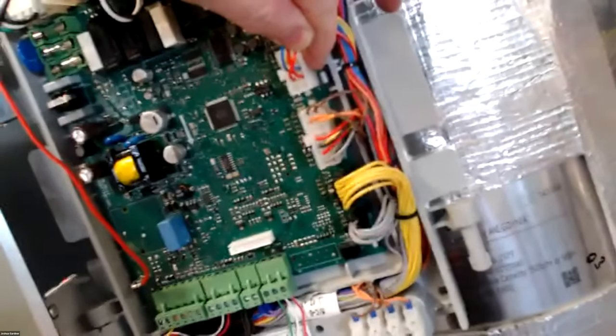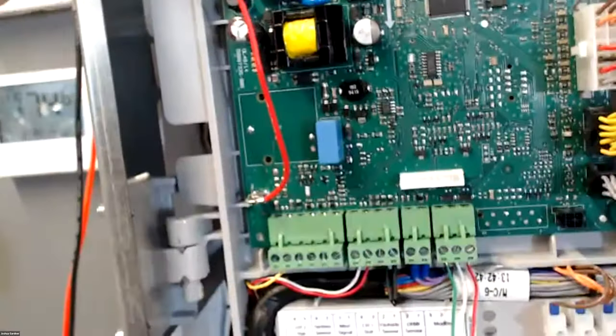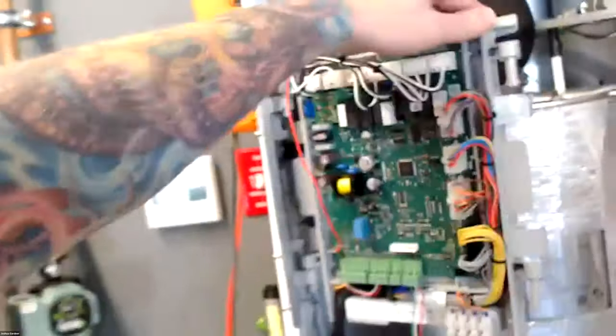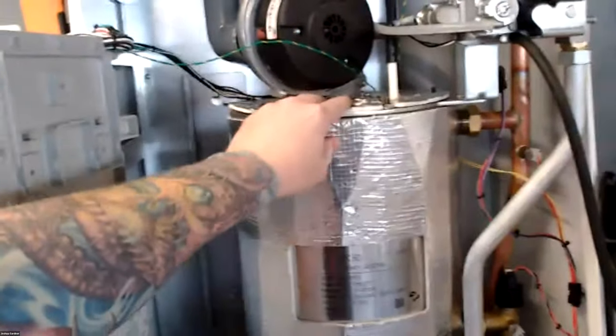The board, if you have to change it, is pretty easy. You just unplug all your connections. And then there's a little clip tab right here holding it in. You just move that over and the whole board just pulls right out. Put the new one in, put all your connections on, and you're done. Also, the control swings out for service. So it makes it easy to get in here if you've got to get into the cabinet, clean the heat exchanger, whatever. Cleaning the heat exchanger, we're running water and solutions. Put this thing out of the way so you don't get any water on it.